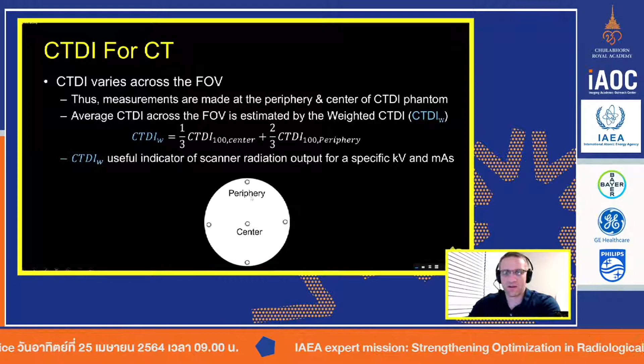Now, why does that not necessarily work once again? Well, consider the fact that these systems don't actually spin a full 360 degrees. They typically spin a little bit more than 180 degrees, maybe 270 at most. If I have a CTDI phantom here with my center and my periphery holes, but the scanner is only spinning under or over, there are certain locations here denoted by the letters A, B, C, D. You can see that depending on whether it spins down or spins up, the values are different at those locations.